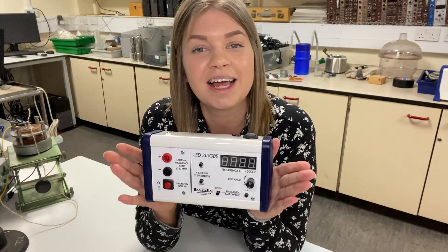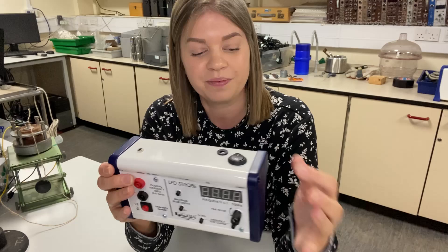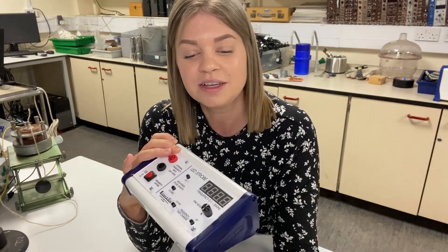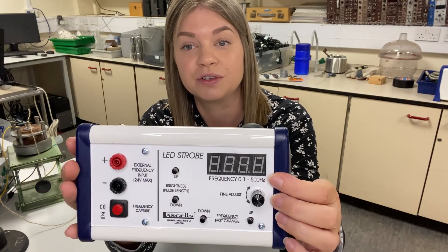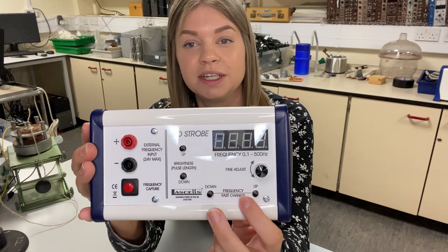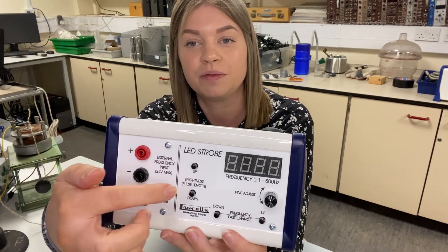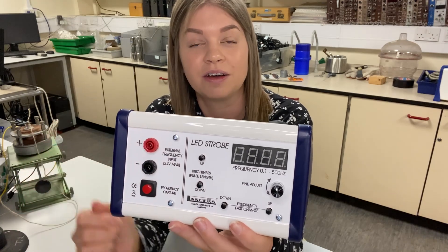Introducing the Lascells LED stroboscope. This unit takes 24 volts input and comes with one lamp module. On the front of the unit the frequency range is 0.1 hertz up to 500 hertz. There is coarse frequency tuning and fine tuning, and a brightness toggle which changes the pulse length of the strobe.